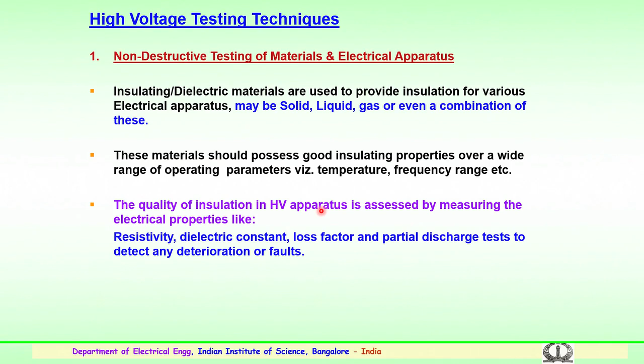The parameters which could affect the insulation resistance, as mentioned earlier, depend upon the nature of the materials used for the insulation and the temperature at which it is operated. The changes in temperature could also influence the contaminants or pollutants which could form on the surface over a period of time. This could cause insulation degradation with the electrical stress and the temperature.